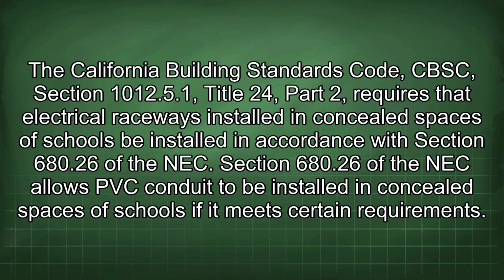The California Building Standards Code (CBSC) Section 1012.5.1, Title 24, Part 2 requires that electrical raceways installed in concealed spaces of schools be installed in accordance with Section 680.26 of the NEC. Section 680.26 of the NEC allows PVC conduit to be installed in concealed spaces of schools if it meets certain requirements.